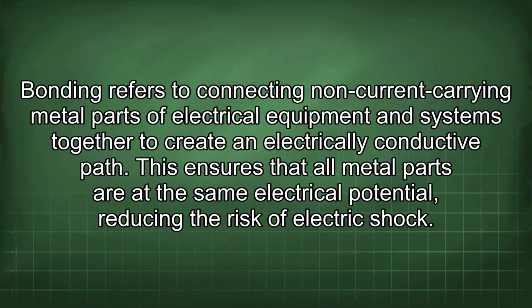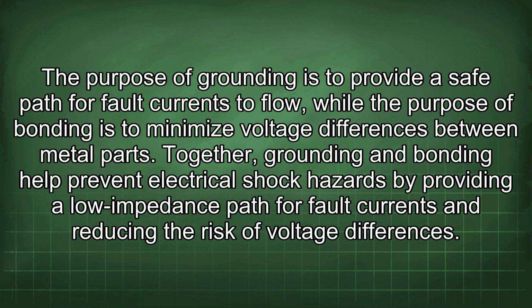Bonding refers to connecting non-current carrying metal parts of electrical equipment and systems together to create an electrically conductive path. This ensures that all metal parts are at the same electrical potential, reducing the risk of electric shock. The purpose of grounding is to provide a safe path for fault currents to flow, while the purpose of bonding is to minimize voltage differences between metal parts. Together, grounding and bonding help prevent electrical shock hazards by providing a low impedance path for fault currents and reducing the risk of voltage differences.